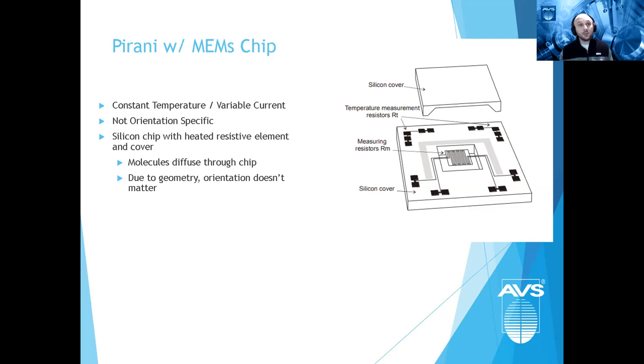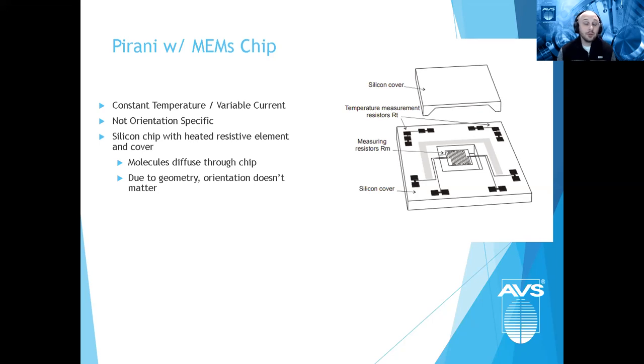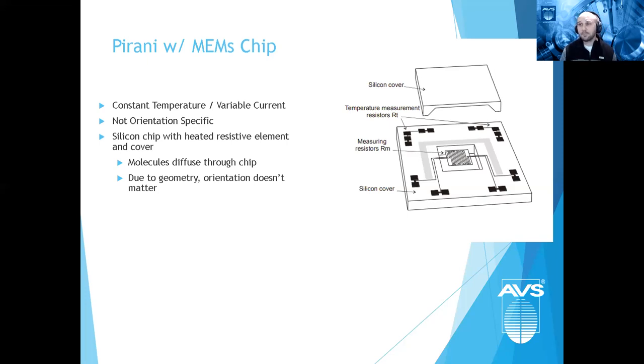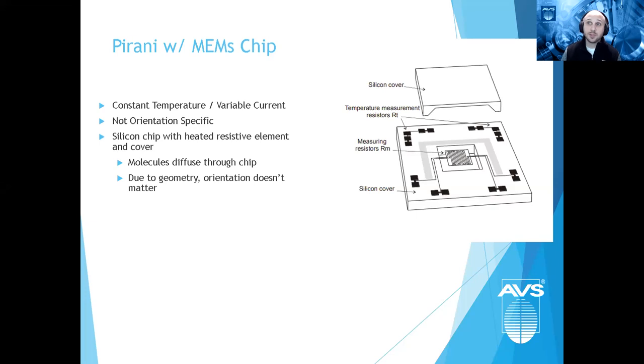Key advantages of the MEMS Pirani: it's not orientation specific and not vibration dependent. Imagine a filament gauge next to a roots blower — the filament vibrates, giving erroneous measurements. With a MEMS chip, that's not an issue. This also makes it easier to mount in hard-to-reach places. The downside is that the increased surface area of the MEMS chip makes it easier to contaminate in processes with condensable vapors.